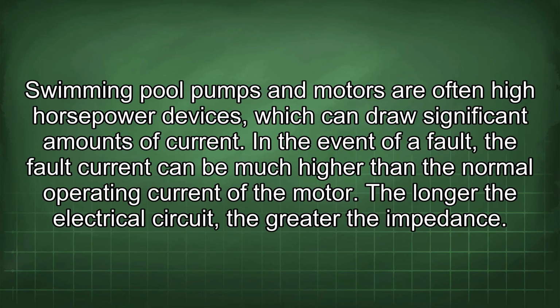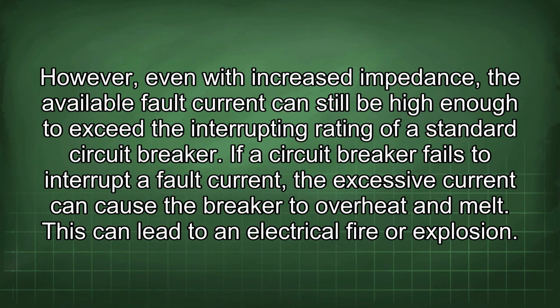Swimming pool pumps and motors are often high horsepower devices, which can draw significant amounts of current. In the event of a fault, the fault current can be much higher than the normal operating current of the motor. The longer the electrical circuit, the greater the impedance. However, even with increased impedance, the available fault current can still be high enough to exceed the interrupting rating of a standard circuit breaker.